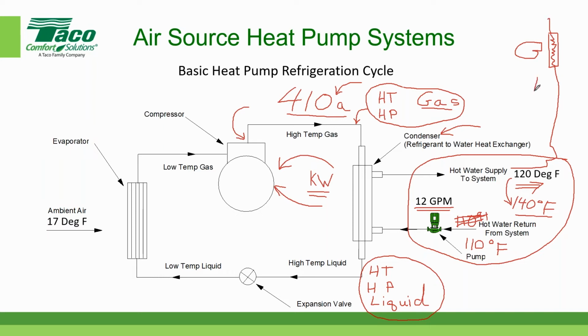And my entering water temperature is, let's say it's 120, like I have in the black lettering, 120 degrees Fahrenheit. And let's say the room air temperature is around 70 degrees Fahrenheit. And then I want to get within 5 degrees. So I select the coil that has a 5-degree approach. And so maybe this temperature leaves here at 115 degrees Fahrenheit. Now you can sort of see where I'm headed: if my water temperature was up around 140 and I had a 5-degree approach, it'd be about 135. So this is the air.